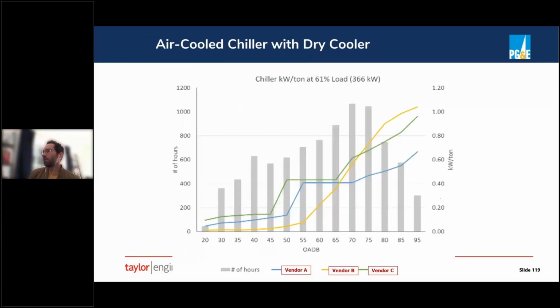This slide is provided just to demonstrate that when you are selecting air-cooled chillers with integrated dry coolers, you need to do your homework on how their efficiency varies with ambient dry bulb temperatures. So these are 3 different options from 3 vendors. And we can see that each of these was selected for some design condition, but a couple of them clearly do not provide nearly as much economizer cooling at middling OA temperatures, so between 50 and say 60 Fahrenheit, as the other does.